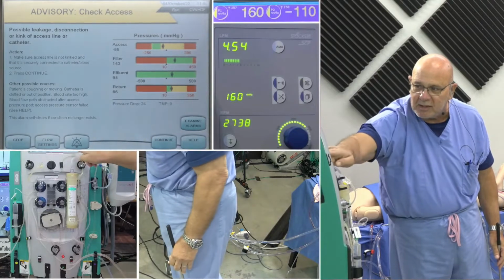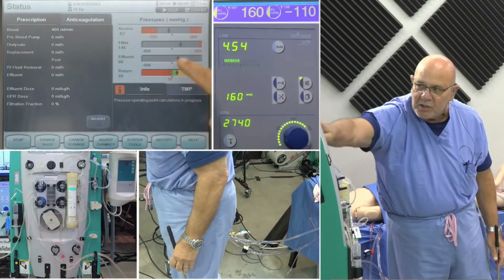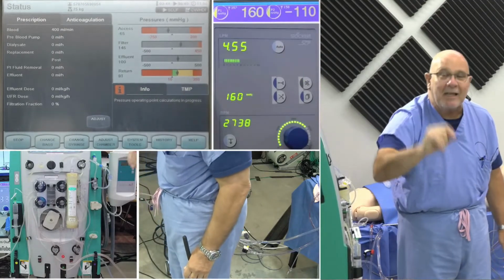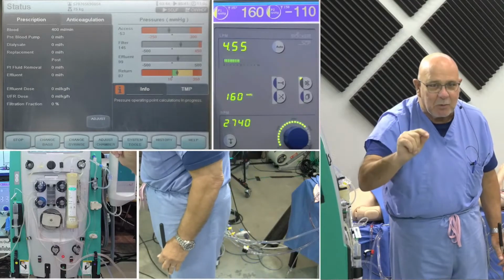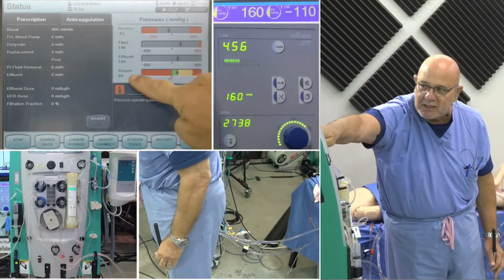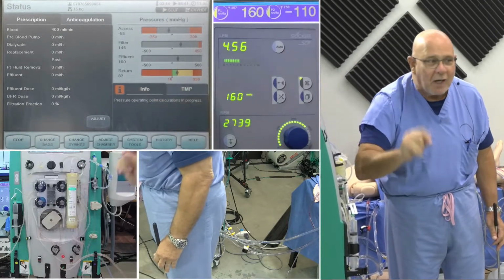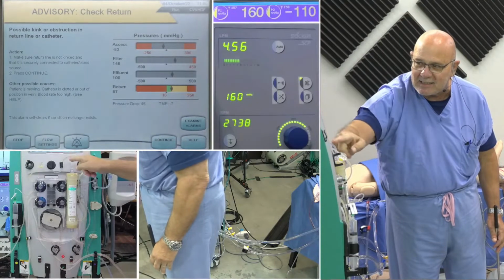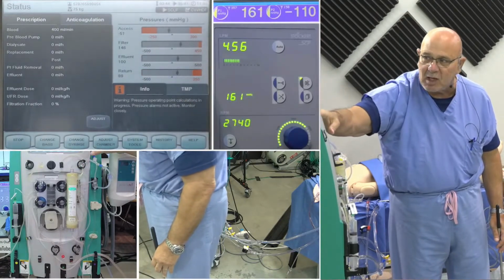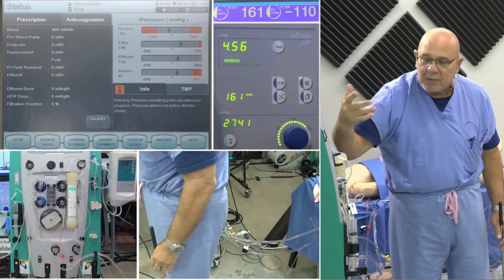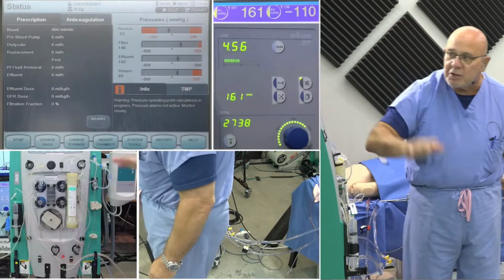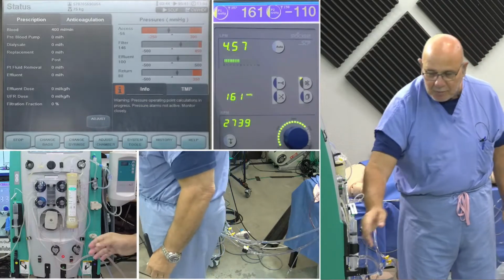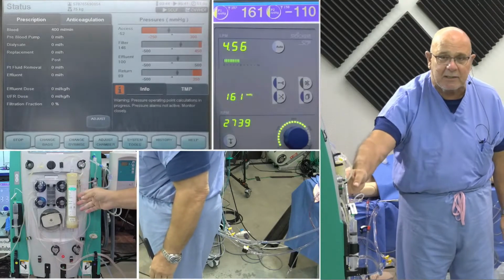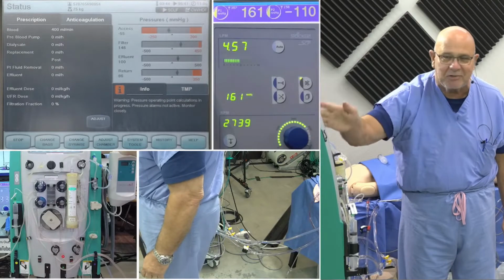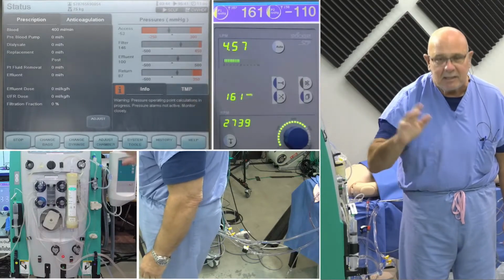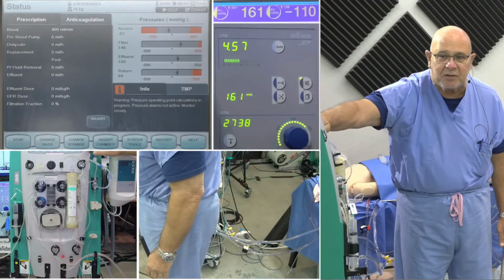And now, if you look at the circuit, just by doing that, you have an access pressure that is negative. Again, that's what you expect it to be. That's what it would be at a temporary dialysis catheter. And you have a return pressure that is positive, what you would expect it to be with a dialysis catheter. And the reason why this machine keeps alarming is because we've changed the pressures so often, but you notice it doesn't really stop. Now, when you run therapies, whether it be pre-filter replacement or post-filter replacement, if you run dialysis with it, one, you shouldn't be using the machine to just run straight dialysis. Be that as it may, different topic for a different day. This device is made for CVVH.